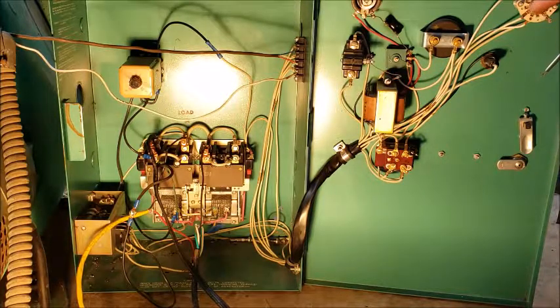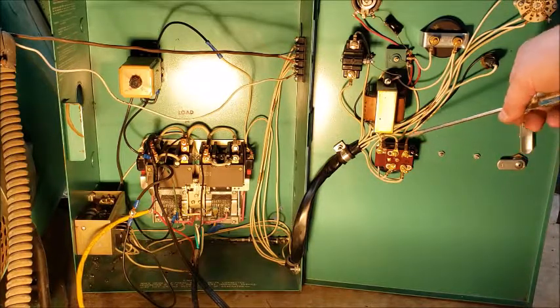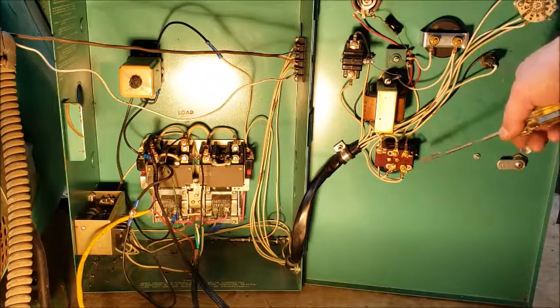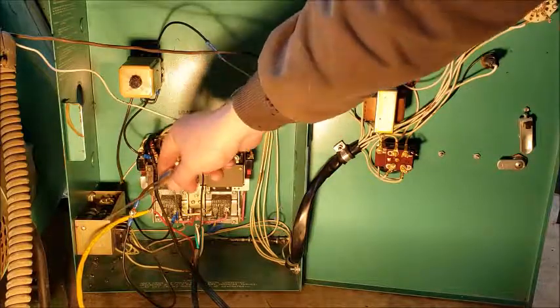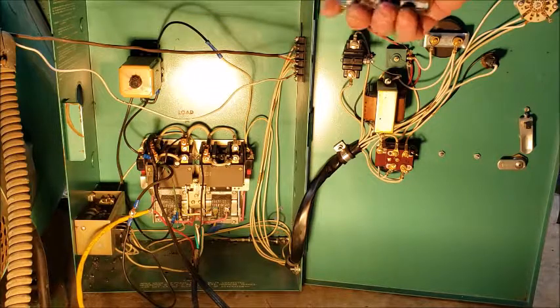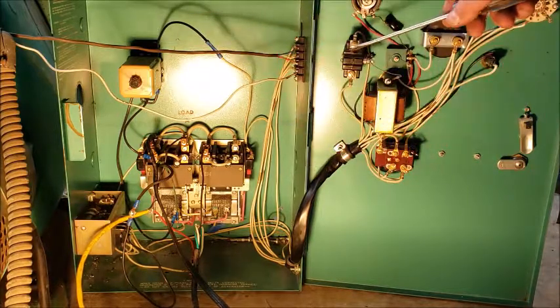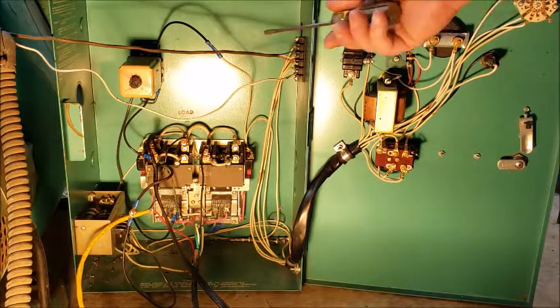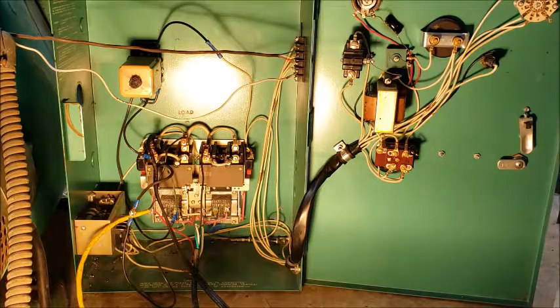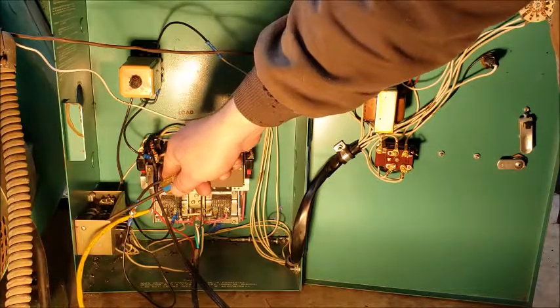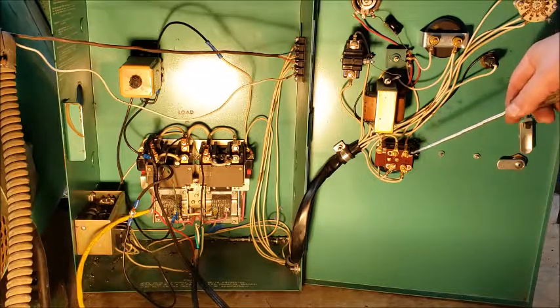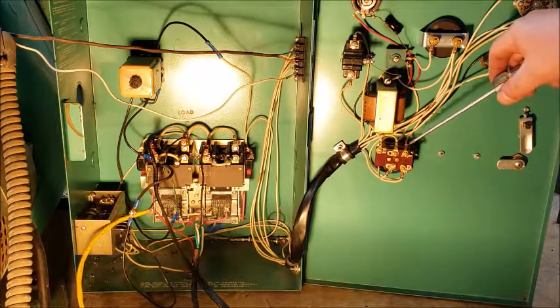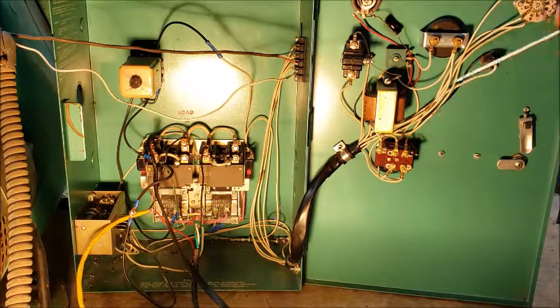And so we start here at this switch. So the center of this is grounded when it's set to auto. The wire comes down here, goes through the right terminal and the left terminal of this relay down here. Then that travels down to the start disconnect box over there, goes through a relay and then back up. It's a crank limiter, and so it goes through that and then up to terminal 3.